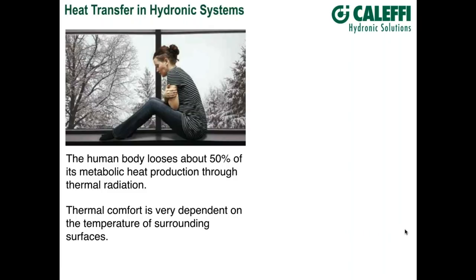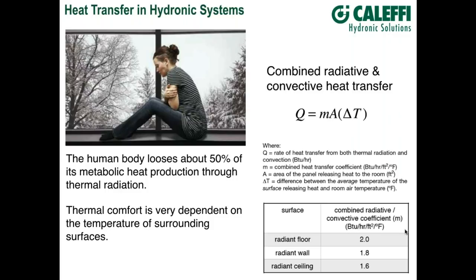Even though the air temperature might be considered comfortable — 68 to 72°F — the surface temperatures around you will have a very profound effect on comfort. This is one of the reasons radiant panel heating has increased in popularity: it creates warm surfaces that drastically decrease the rate of heat loss from your body by radiation.